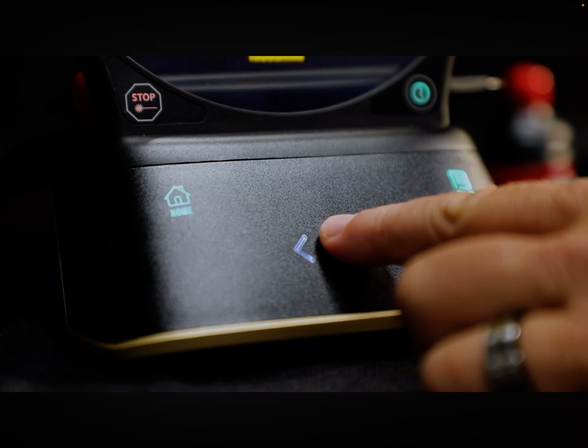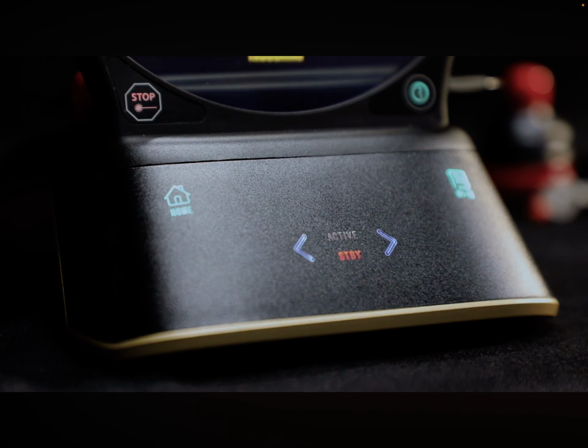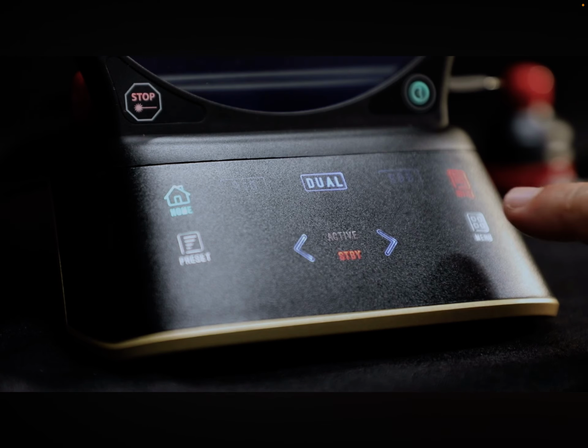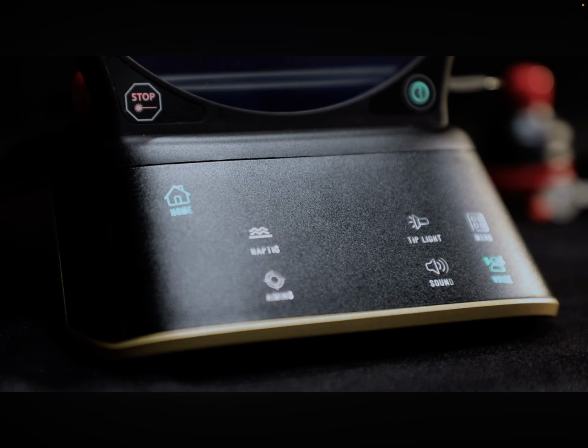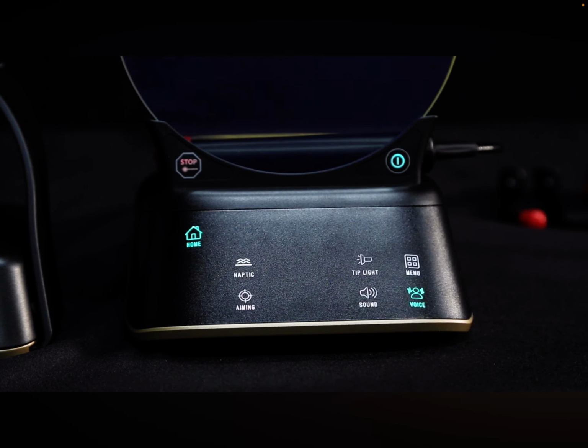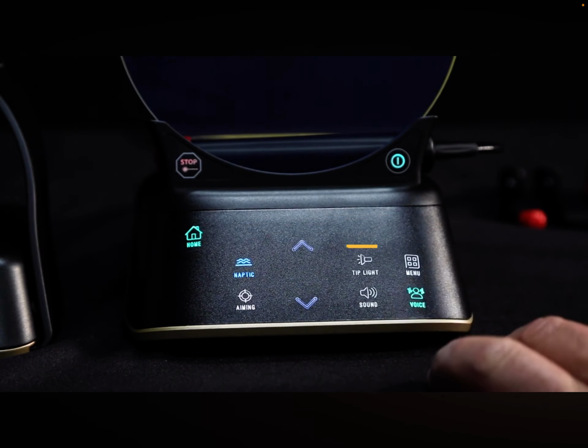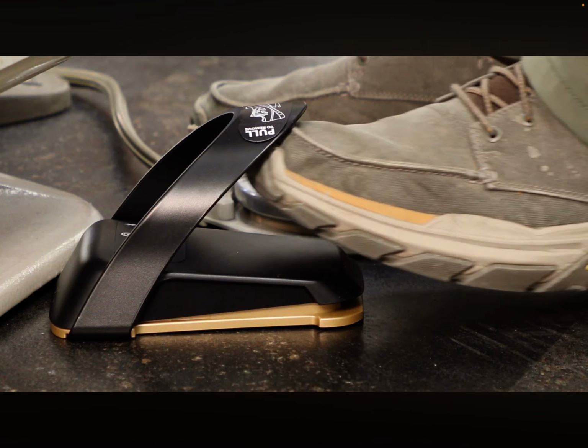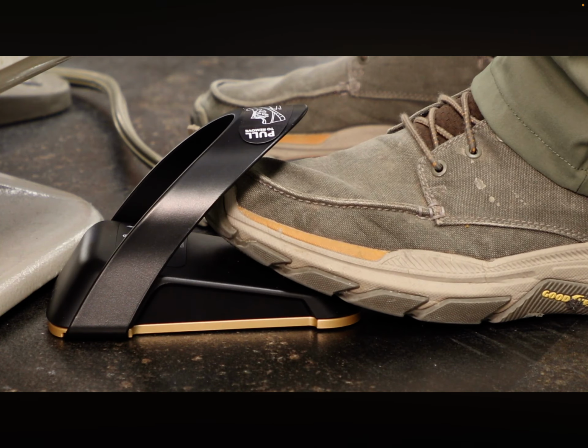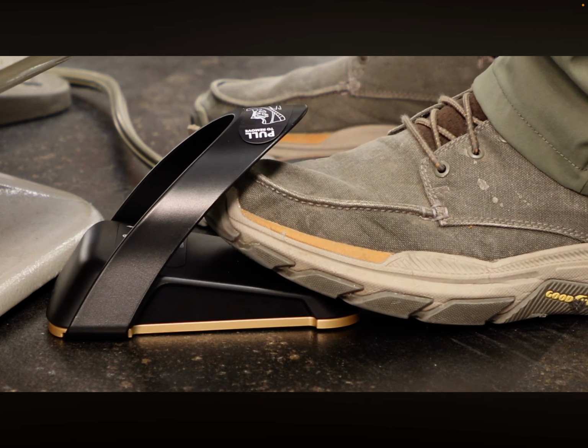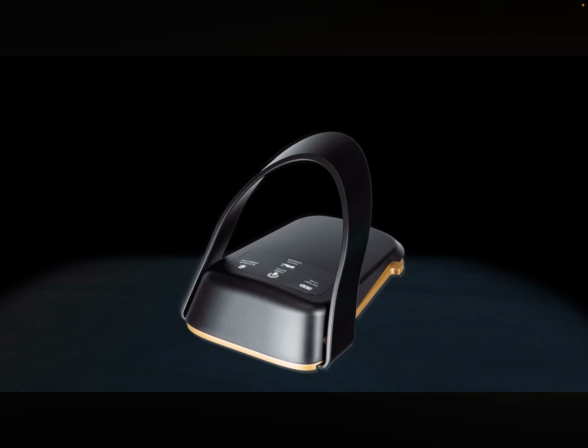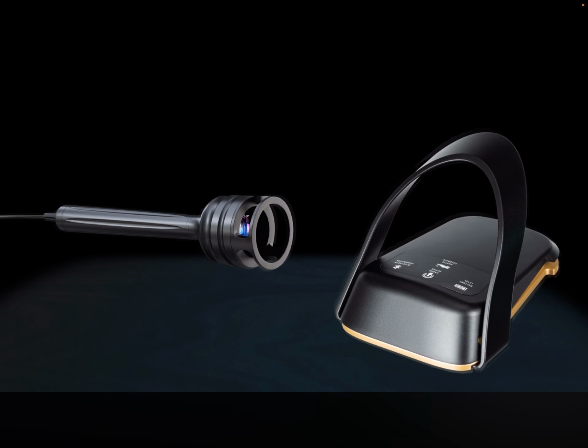The unit is designed with Guided Touch Interface, or GTI. As you operate the Gemini Evo, only relevant icons light up to help guide you through the interface and make proper input selections. Pressing the menu button brings up the options for haptic sense, aiming light, tip illumination, and sound settings. The Gemini Evo foot pedal is equipped with haptic sense. As you press the pedal, you will feel a buzzing sensation to the foot while the activation pedal is depressed. The handpiece is also equipped with haptic feedback in the PBM mode to provide the patient with the same sensation to let them know when the treatment cycle has started and ended.